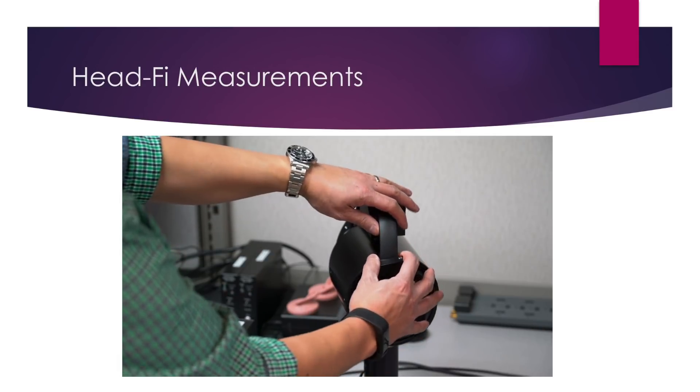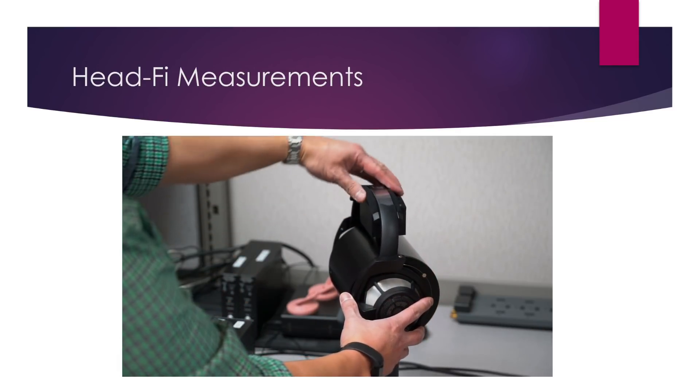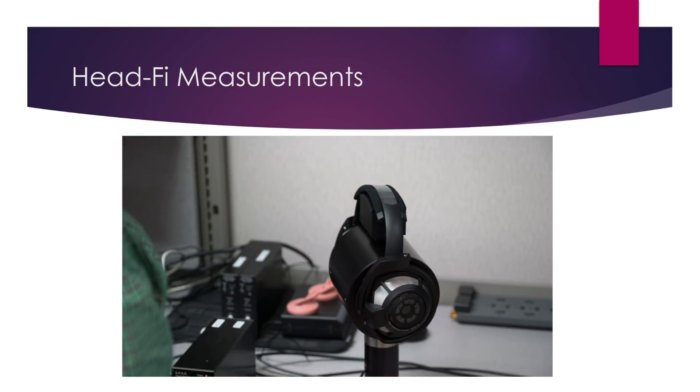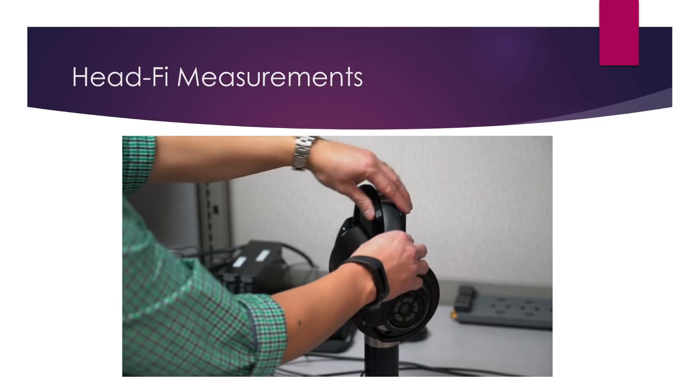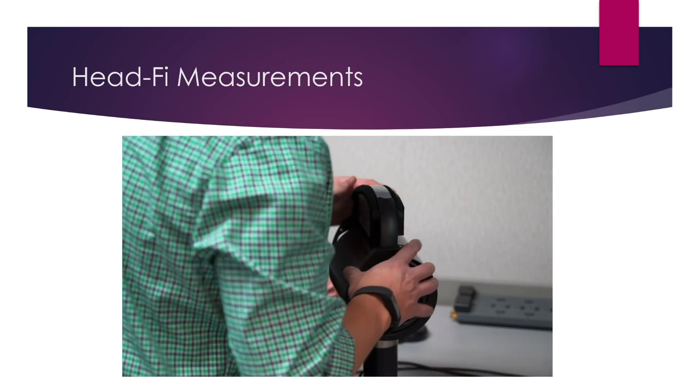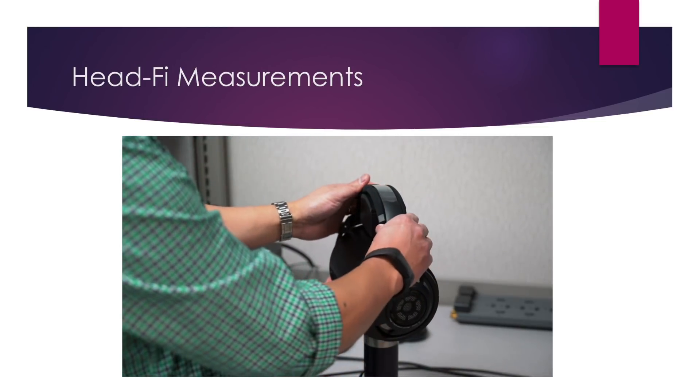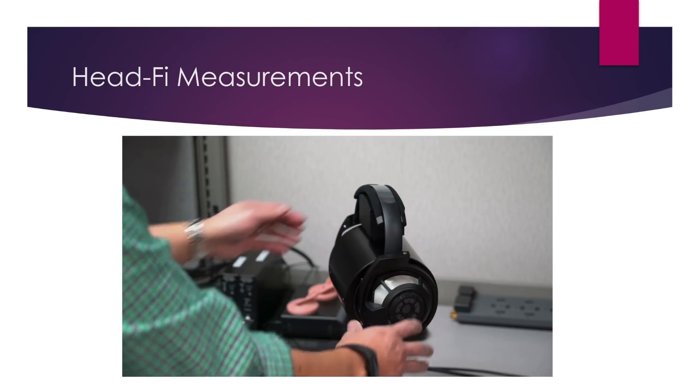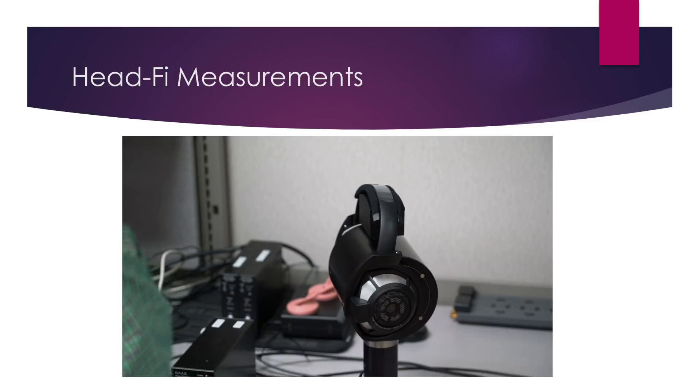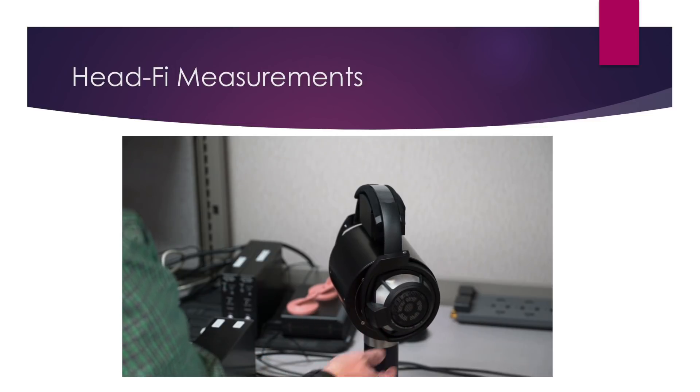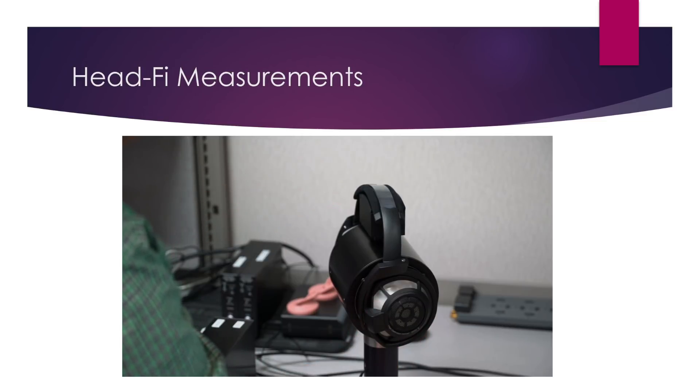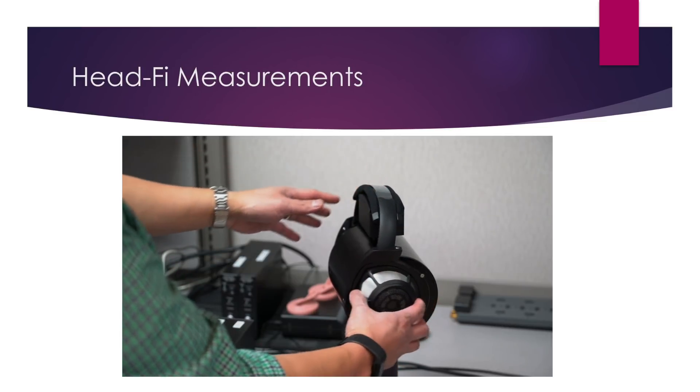When you have this much latitude, then you have to know where proper, more human-like placement is, and that actually was helped along a great deal by our experience with KEMAR. So the ease of getting a seal with the 45CA is great, and measurement workflow is faster for sure, but the caveats are that you have to understand the range of realistic placement with it, and sometimes bass can be slightly exaggerated due to such easy sealing on the flat cheek surface. Again, with our GRAS 45CA, we've updated the pinna to the new anthropometric pinna, and also updated the ear simulators to GRAS's latest high-resolution ear simulators, the GRAS RA0401.